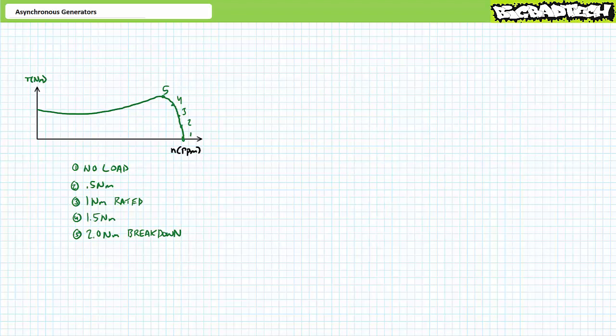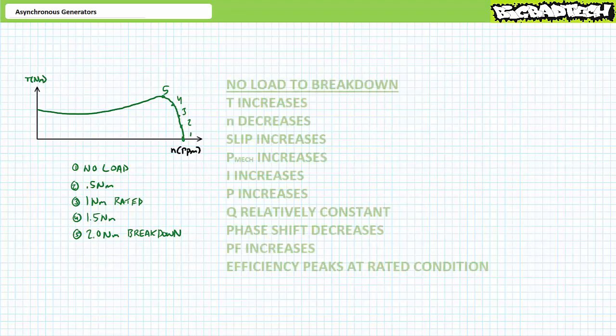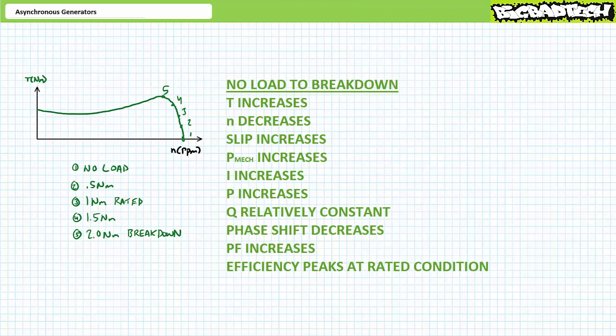We should expect some predictable results as we travel from a no-load condition through the rated condition to breakdown. As torque increases, speed will decrease, slip will increase, and mechanical power will increase. Electrically, we should expect current magnitude to increase, real electrical power input to increase, reactive power to remain relatively constant, and phase shift to decrease corresponding to increased power factor. Lastly, we should observe zero percent efficiency at no-load conditions, increasing efficiency as we load the motor, peaking at or around the rated condition, followed by decreasing efficiency as we approach breakdown.